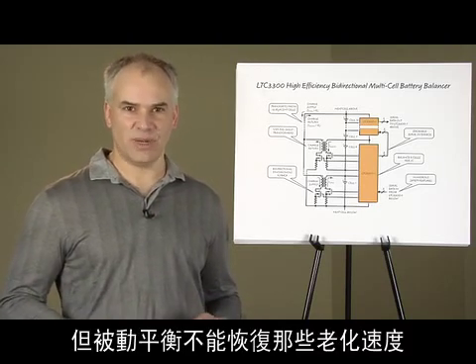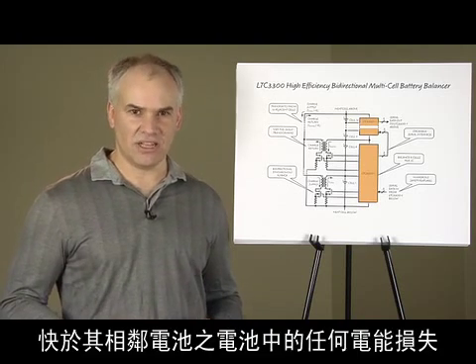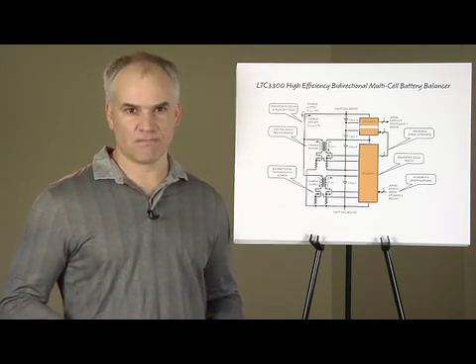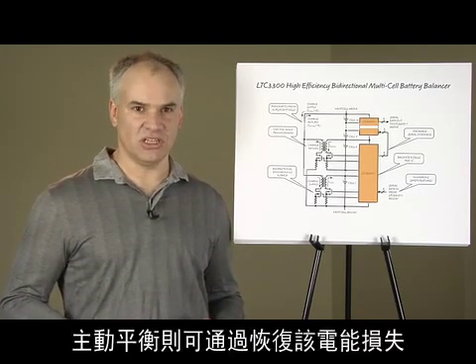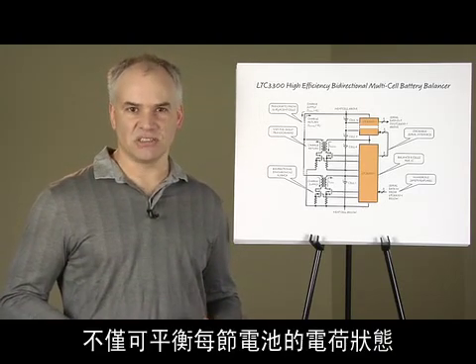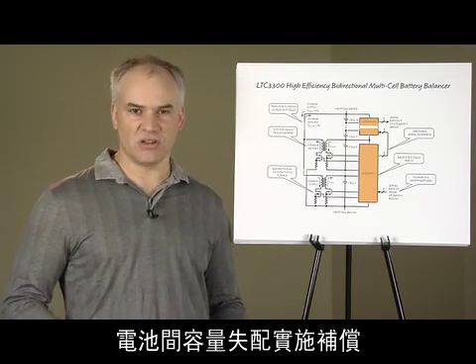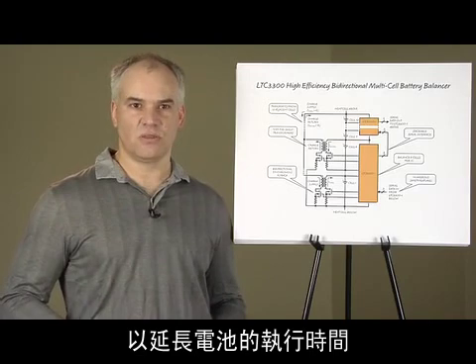However, passive balancing cannot recover any lost energy in cells that have aged faster than their neighbors. Active balancing, by recovering this lost energy, not only equalizes each cell's state of charge, but also extends battery run time by compensating for cell to cell capacity mismatch throughout the stack.